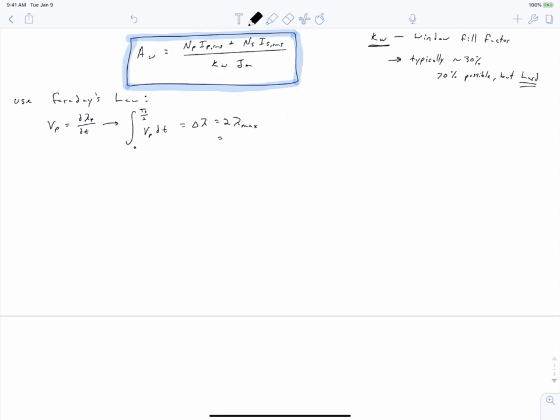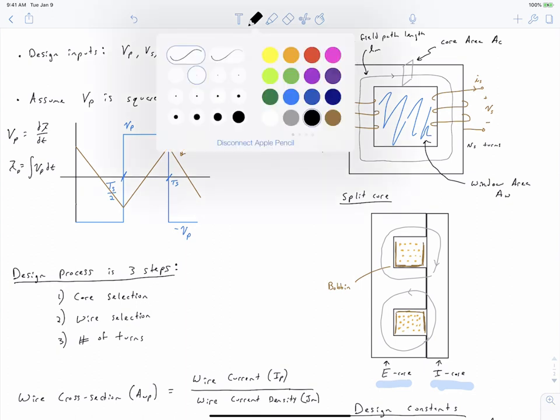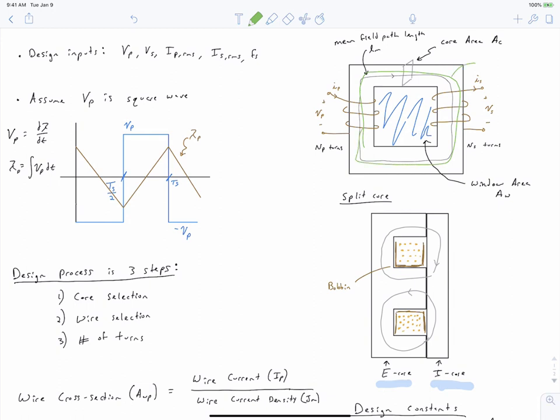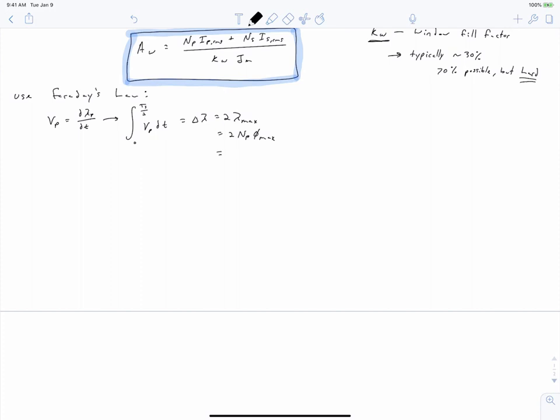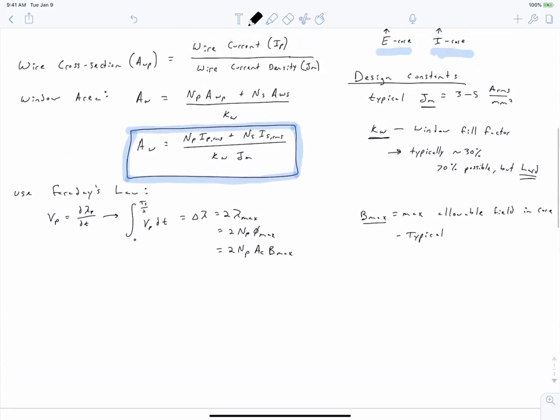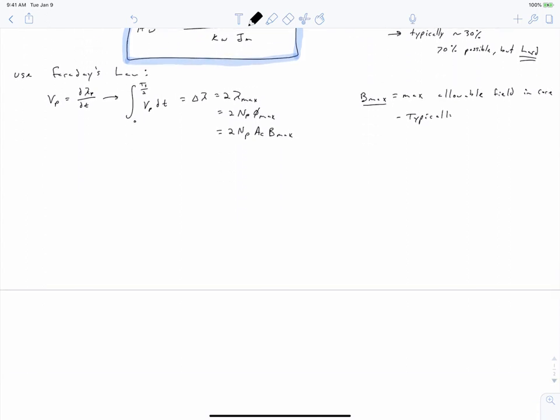This equals the ripple in our flux linkage, which is 2 times the maximum value of flux linkage. Recall that flux linkage equals the number of turns times the core flux, and flux equals area times field (B). We've now arrived at our third design constraint: we're going to specify an assumed maximum flux density Bmax in our core for rated conditions. Just like we had a maximum current density, we also have a maximum flux density, typically less than 1 Tesla.